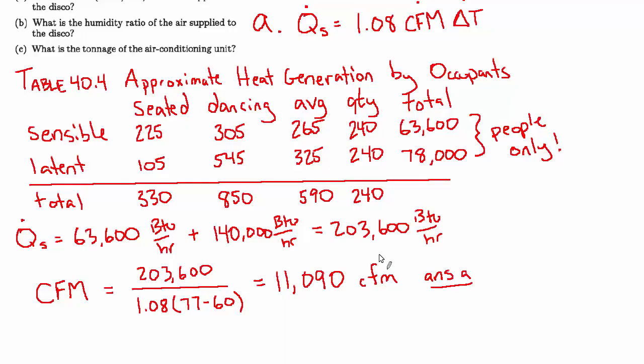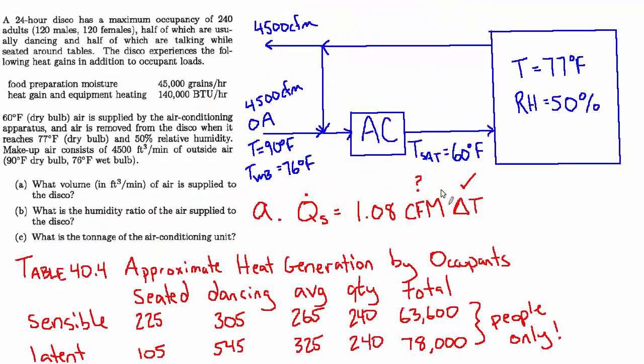So now we know the airflow that we need. The next question is: what is the humidity ratio of the air supplied to the disco? We have this 11,000 CFM of supply air. Now they want to know what's the humidity ratio of that supply air.